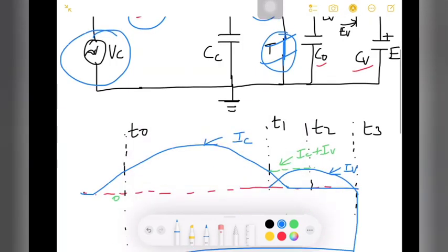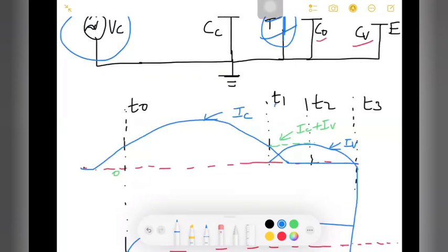At a time T1, just before the zero of the generator current, if you observe, this is my generator current which is flowing, which is going to become zero after a few seconds. Before that, your master circuit breaker 1 will start here, which clears the generator circuit before the IC becomes 0. That is going to happen here.